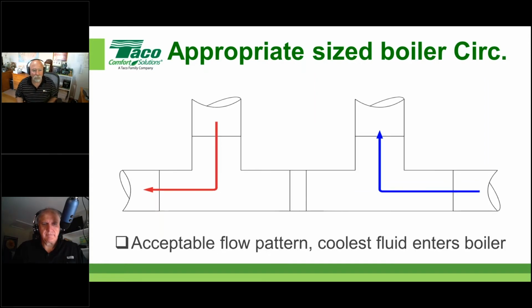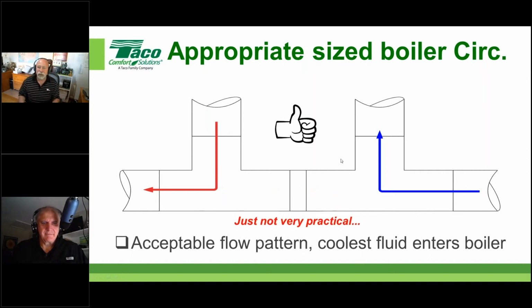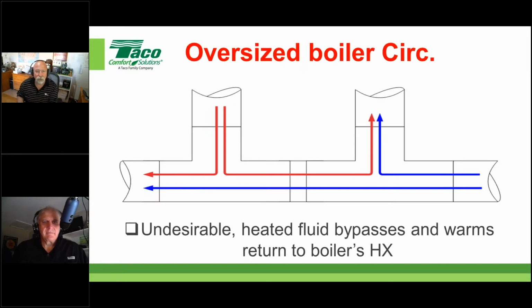Well, what else is out there? Here's an acceptable flow pattern. If I could get all the water to go through the heat exchanger, be heated up, and come back out here. Everybody goes, yeah, that seems right to me, but think about this configuration. Notice I have two T's here, and I also have two circulators, one up here and one out here. What's the practicality of getting both those circulators to give you exactly the same GPM? It's very hard to do. It's just not very practical. So we say, if you're going to do something like this, you might as well get rid of that, put two elbows here, and pipe it in series with a single pump, as long as the boiler manufacturer gives you the blessing to do that. Now let's show you when things get a little rough here.